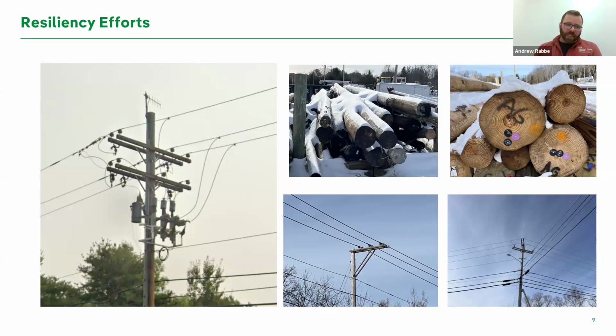Another thing the company's been doing is something called tree wire, which is a coated conductor up in the air. The original wire was either copper or aluminum, and it was bare. The wire that's right underneath the 3 wires on top is your system neutral. So if you had a tree branch come down across a bare conductor and contact that bare conductor up top with the system neutral, it would short it out, and that would cause a fault.